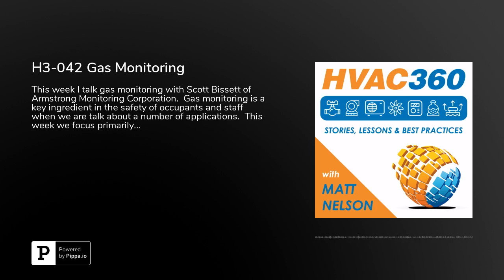Right. Now, what about mounting height? Well, mounting height is again one of these topics where there's a little bit of a bone of contention in our industry. With carbon monoxide sensors, we're all generally in agreement that somewhere between 3 to 5 feet, in the breathing zone, is the most appropriate place to be putting carbon monoxide sensors. When we're dealing with NO2, or nitrogen dioxide, there is a fair amount of discrepancy. Some manufacturers are recommending having the sensors mounted at the top of the space, 18 inches from the ceiling, while others are recommending 18 inches from the floor.